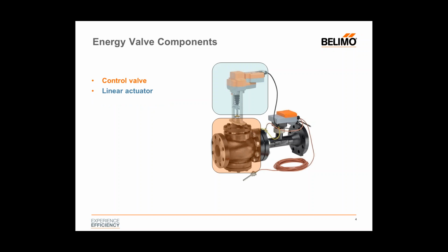This actuator itself has a lot built into it. First of all, it has an integrated web server. That integrated web server allows you to connect to a valve over a TCP/IP connection for remote setup and remote monitoring. There are valves located in our Hinwil, Switzerland home office that I can connect to from my office here in Danbury. So it allows me to look and see what's going on with the valve in real time, and look at flow. I can look at delta T and many other parameters, again, in real time.